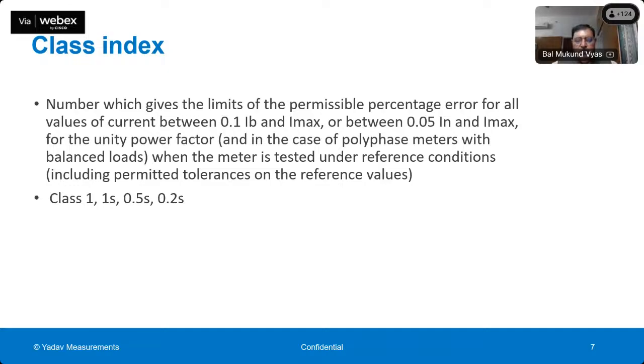because all these influence quantities affect the accuracy of the meter, and of course there are limits specified for these influences, as we will see further. But what is important to understand is that if our meter is not paid attention to, meaning it is not installed in good condition, it is installed at, let's say, very high temperature or at very low temperature, it is getting lots of harmonics, it is subjected to an electromagnetic high frequency field, then it is not going to give me correct measurement. So this is very, very important to understand. In spite of the meter having been tested for accuracy, it may not give you the correct measurements. So all these influence quantities will affect the measurements.